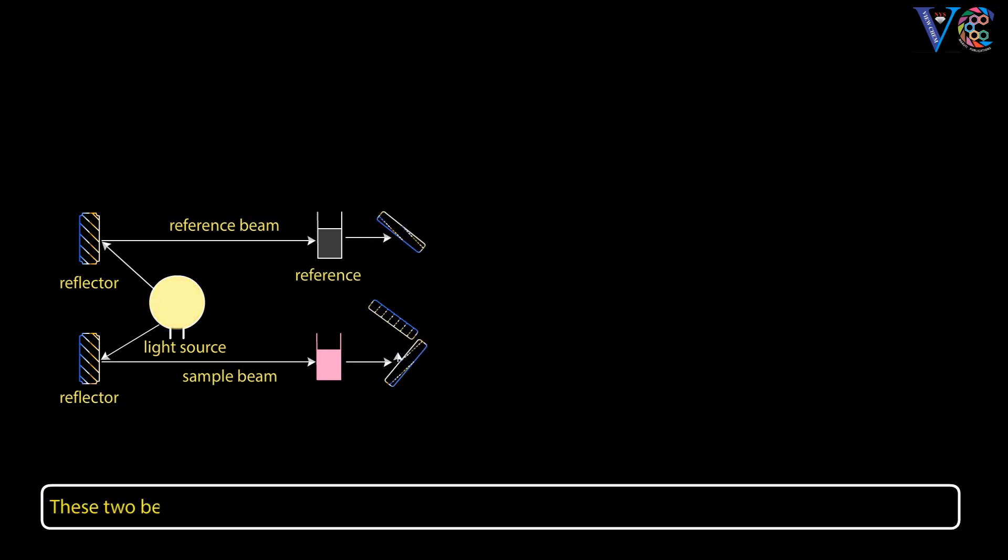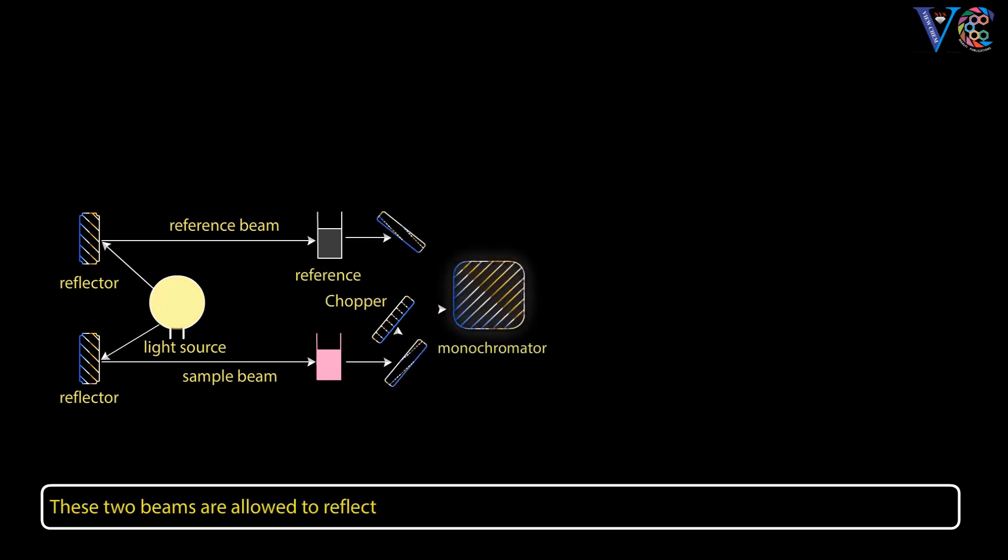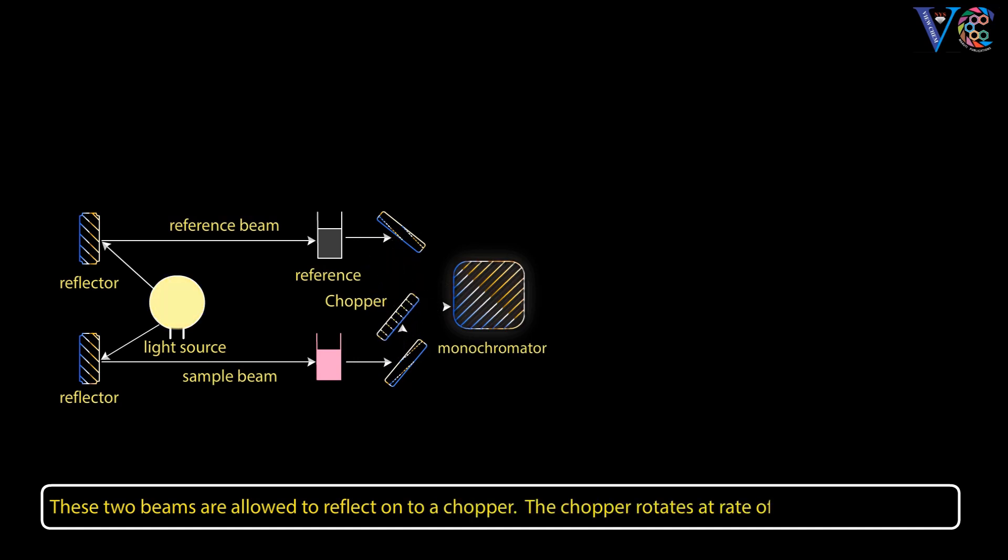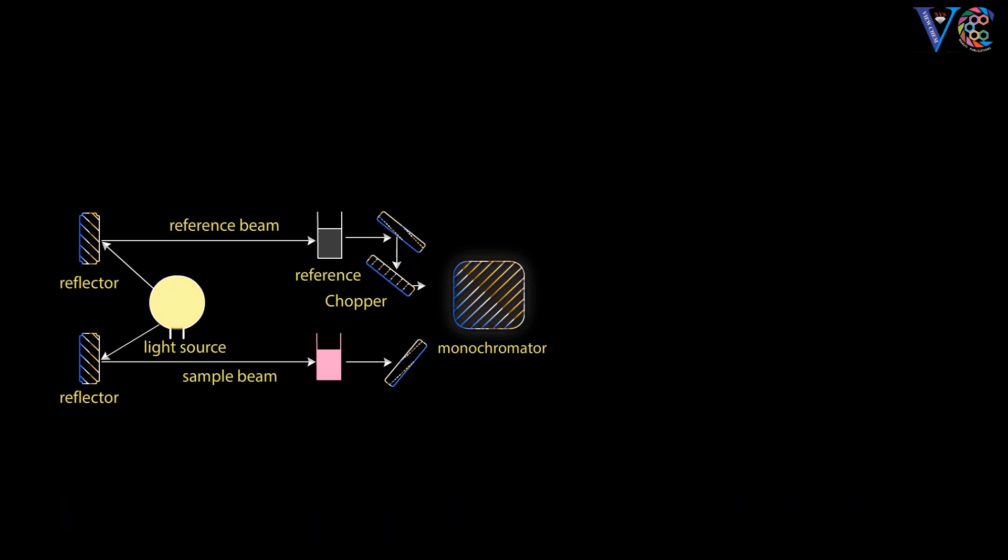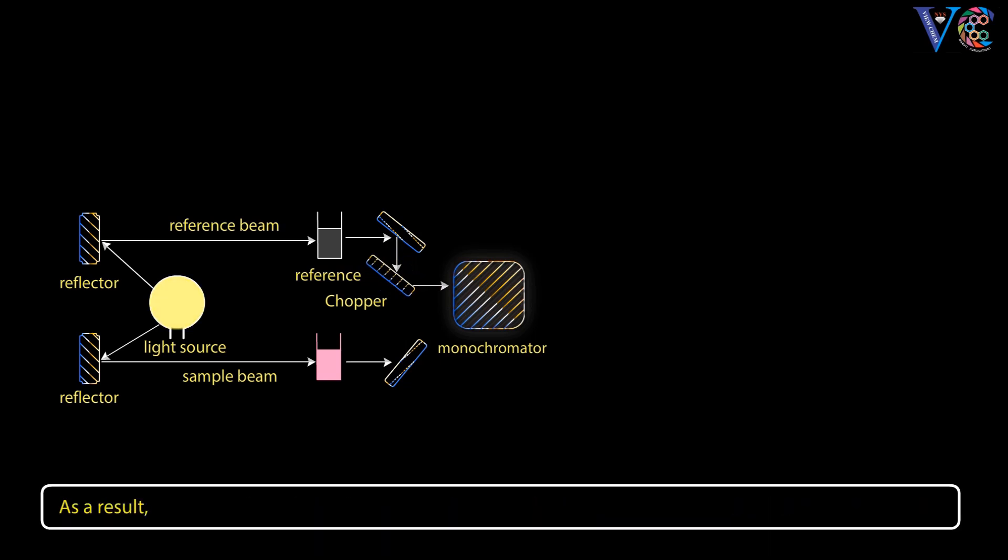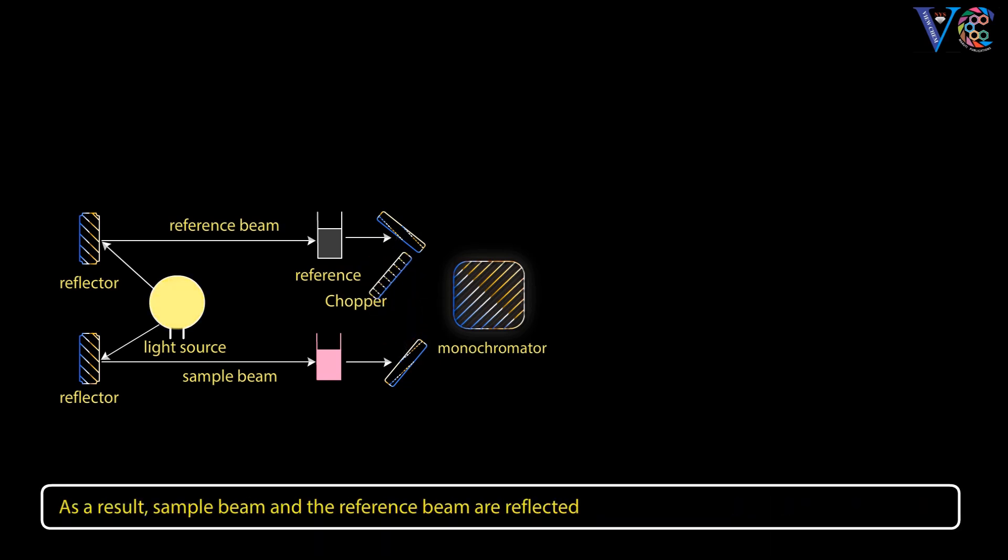These two beams coming after absorption are allowed to reflect onto a chopper. The chopper rotates at a rate of 10 times per second. As a result, sample beam and the reference beam are reflected onto the grating in an alternating manner.